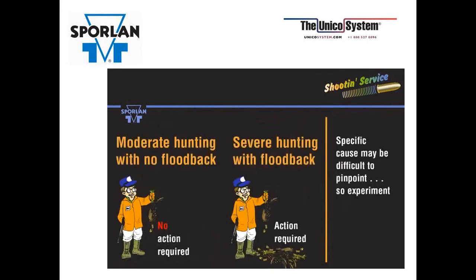And then just to back up a little bit with this hunting and cycling, if it's moderate hunting with no flood back, then you don't really need to do anything. Just try to find the best superheat where you don't flood back and you don't overheat. And if you have severe hunting with flood back, then you're going to have to do something because you're sending liquid back to your compressor. And the specific cause is a little difficult to pinpoint, so you're going to have to do some experimenting.